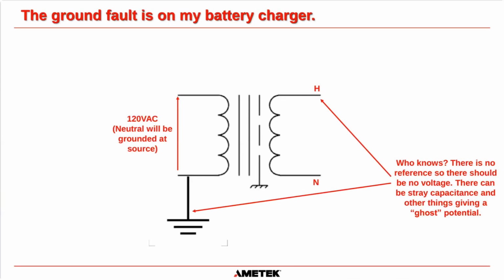On the previous slide, I said if you go from the hot on the primary to the neutral, or the hot to the ground on the primary, you will get 120 volts. But if you go from the hot to ground on the secondary, there should be no voltage, okay? There's no reference to that ground circuit.